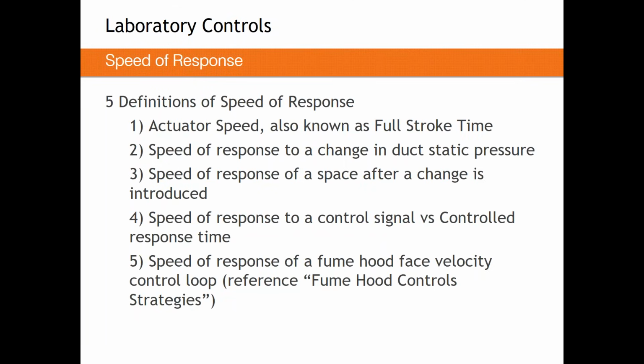The next definition is the speed of response to a change in duct static pressure. So we actually introduced this comment earlier on when we talked about 3 fume hoods manifolded together. When you look at high accuracy terminals and VAV boxes, with high speed actuation and high speed controls, they can move very, very quickly. So when your duct static pressure changes, whether it's a small change or a large change, we can accommodate that change quickly. Quickly usually means a second to 2 or even 3 seconds. However, for a venturi valve, that change can happen instantaneously or nearly instantaneously. Because there's no actuator involved in the system whatsoever and no controller at all, that change in duct pressure will be taken up mechanically and instantly.